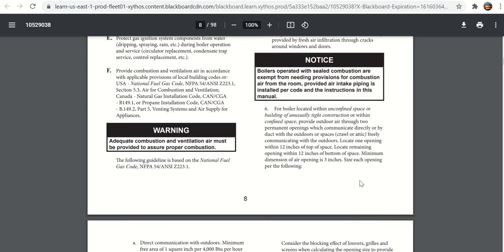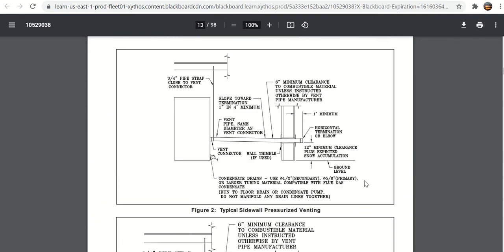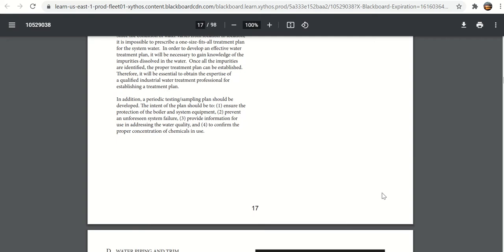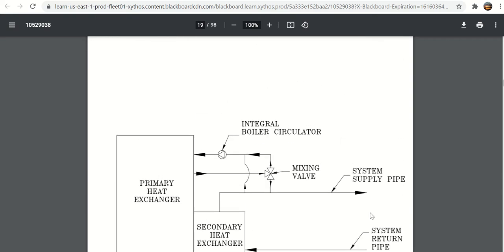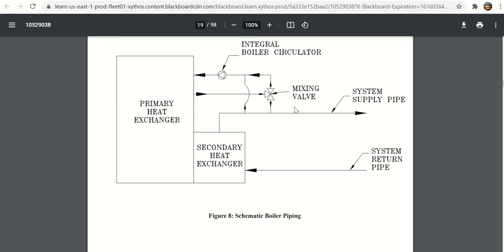This manual goes through, there's a lot of detail there on dimensional information, proper venting of the flue, the heat exchanger. Here's where your system return water comes into the secondary heat exchanger and goes back out to the system supply, but it also will come up and go through. Here's the pump, takes the water from the secondary heat exchanger up into the boiler and then back out that way. When you need the temperature of the water going into the boiler to be hotter, it can recirculate some water right here and not pick up as much water here to keep the primary heat exchanger from condensing.